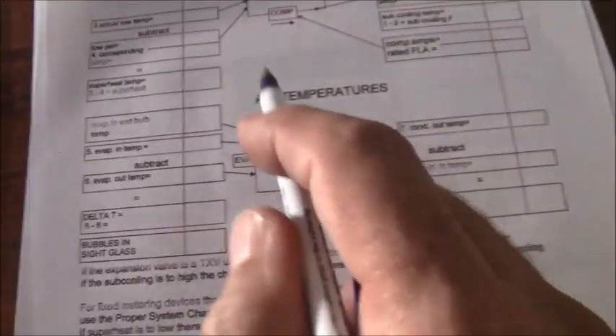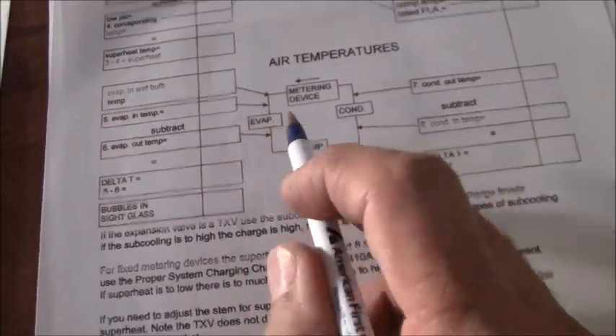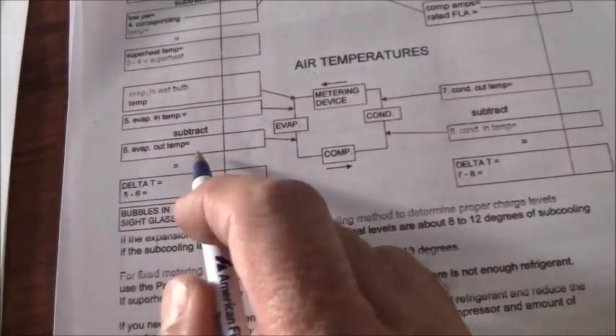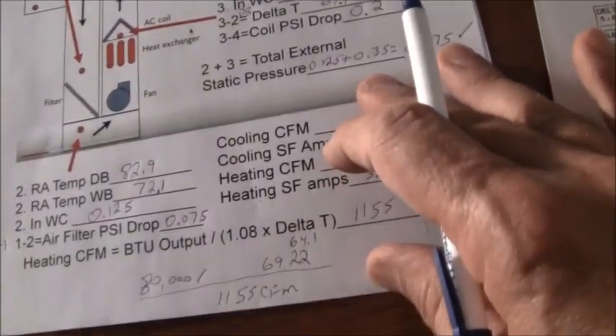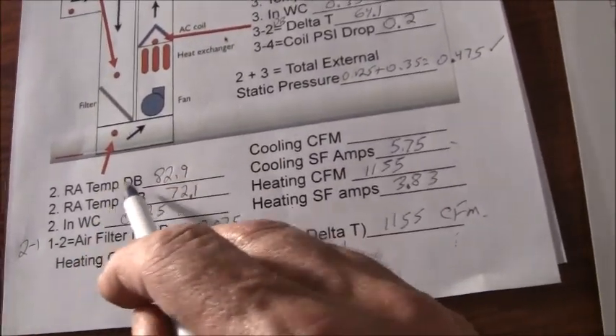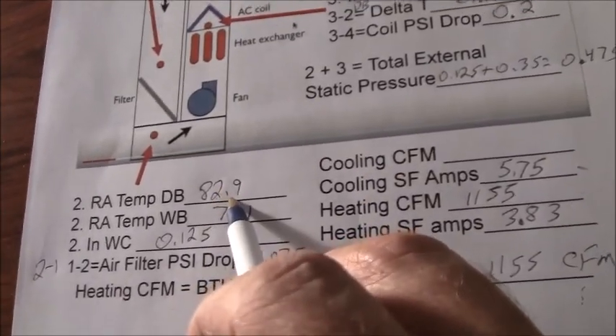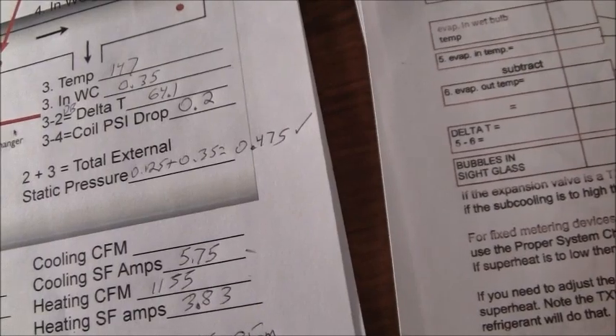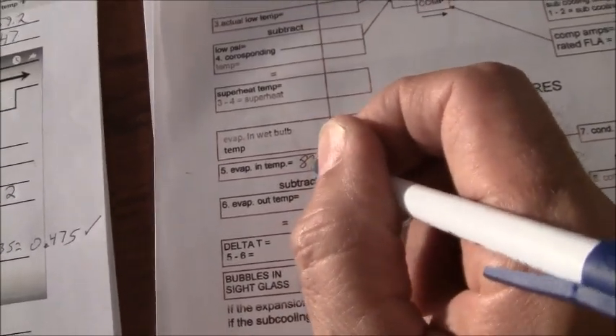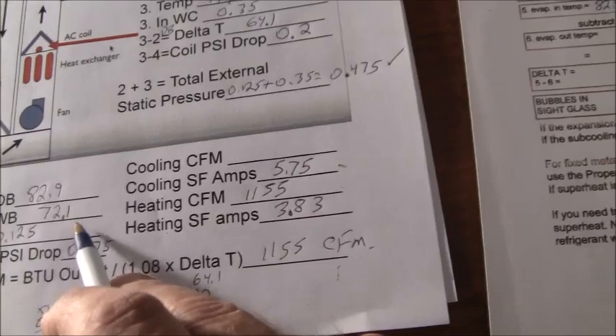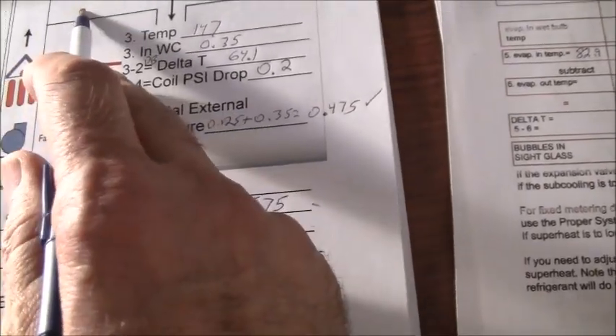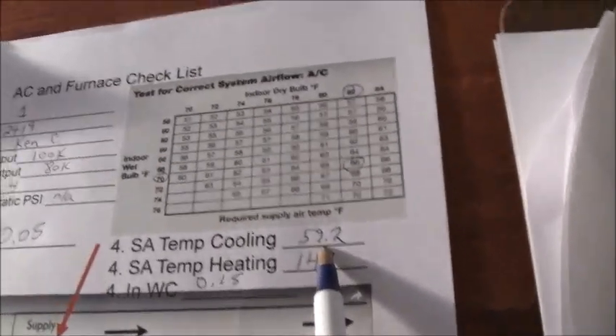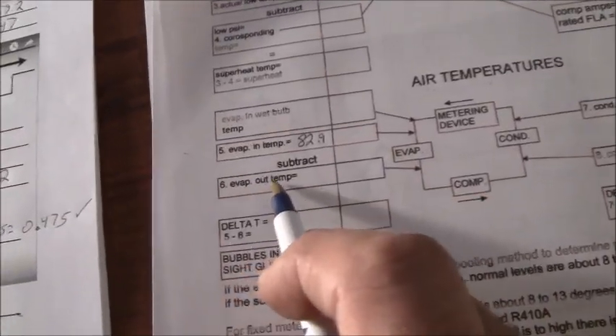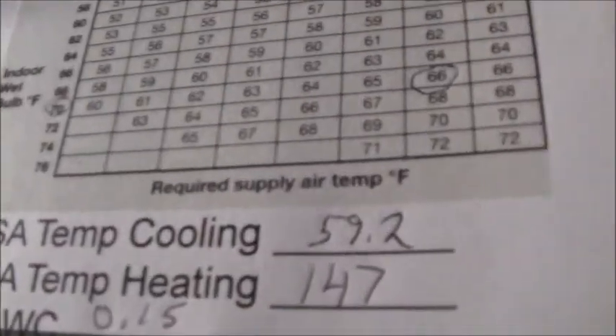We get those outside. Let's focus on the air temperatures. We are at the evap coil. What we want is the inlet and the outlet temperature. We can get those directly off of this sheet right here. The inlet to the evap coil is this one right here. That's going to be 82.9. So the evap coil inlet temperature is 82.9. Write that down right here, 82.9. And the outlet is going to be after here, this temperature here, that's going to be 59.2, supply air temperature. So the evap out temperature is 59.2.